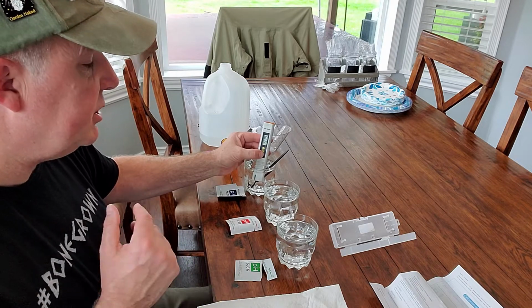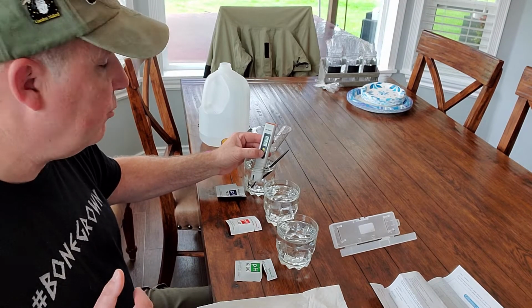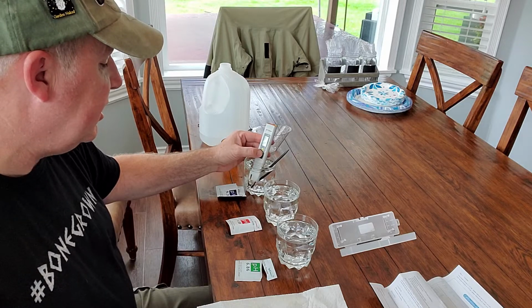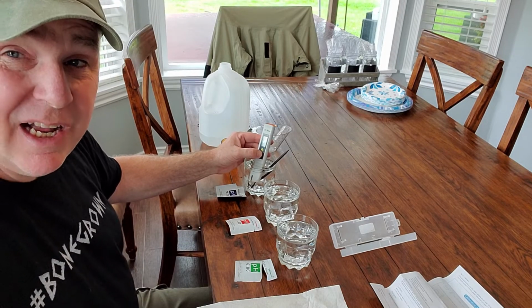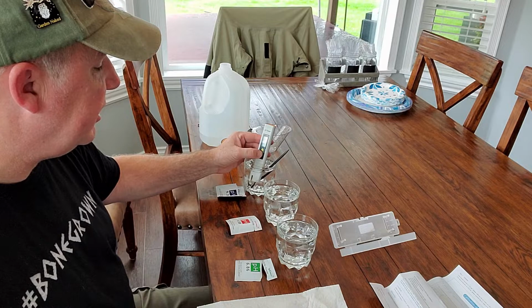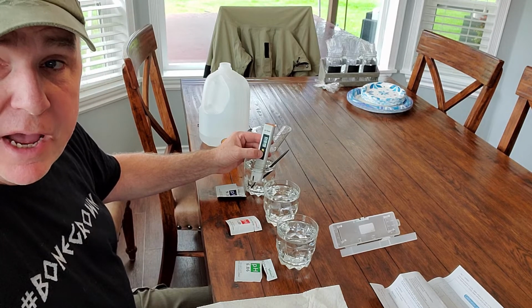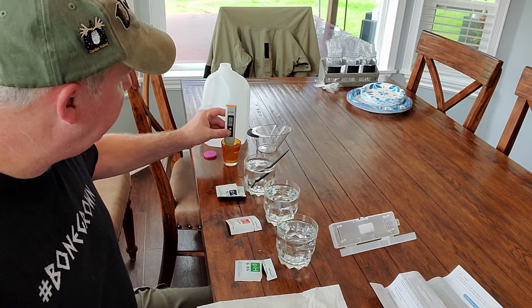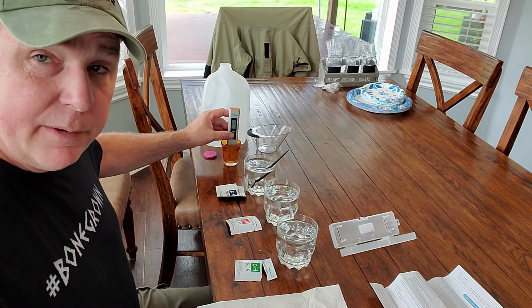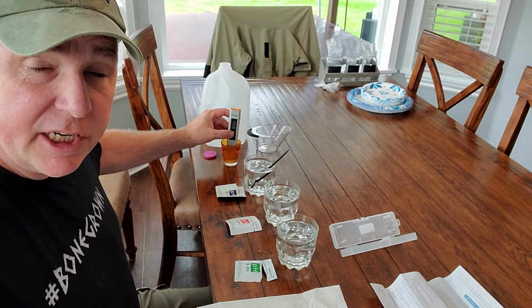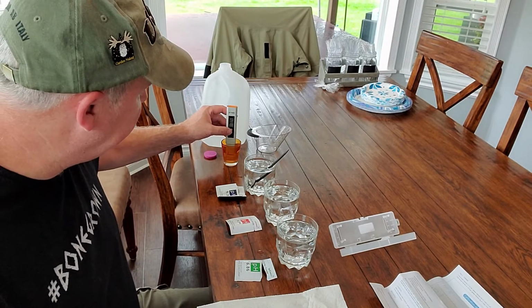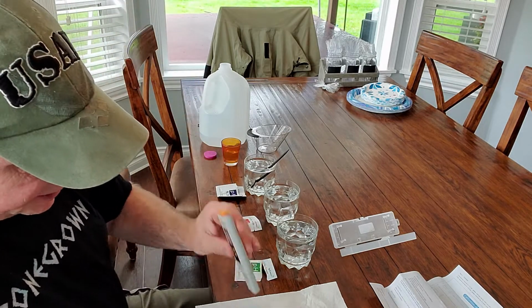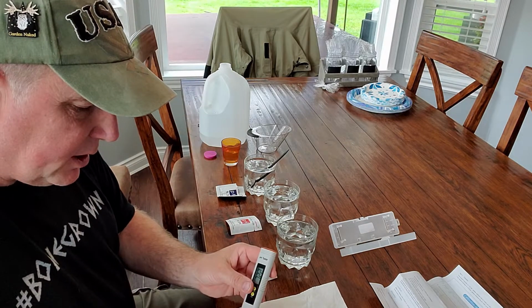Now again, this one jumped up to 9.19, so that's within 1/100th of accuracy. And that means I'm pretty happy with what I'm seeing. So I'm going to rinse this off. Now I'm going to do a little sanity check. I want to see if my calibration really is in line. So I shake this off and dry it off.